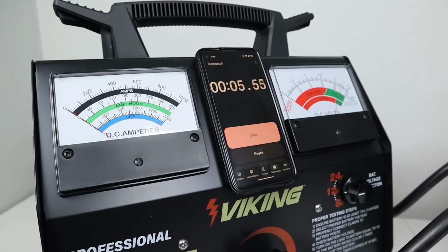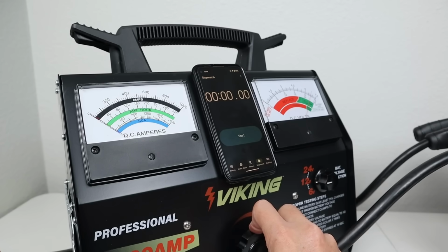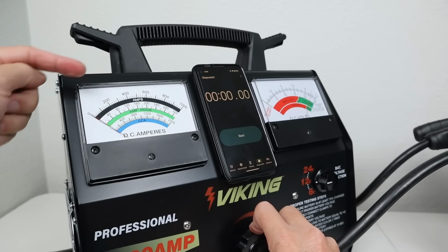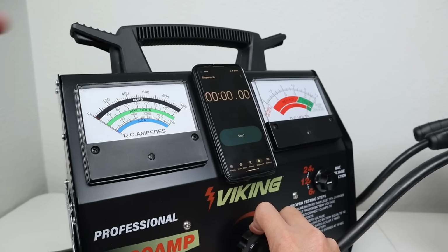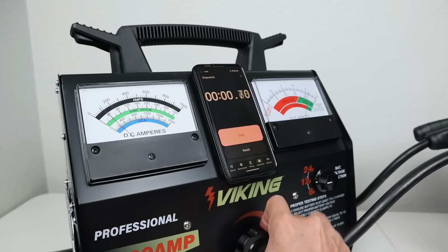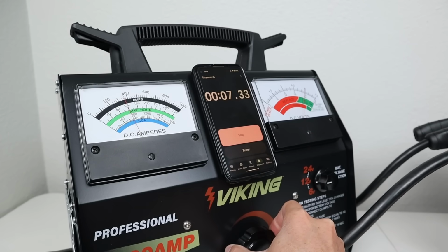Nope, it does not shut off. Now I want to do one last test with my load tester here. I want to see if we can pull about 350 to 400 amps and see if it will actually shut off. Let's go ahead and start this, turn it up to 350 amps, and see if the BMS shuts off. I'm not going to go longer than 20 seconds on this test.